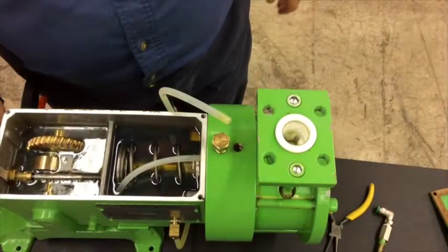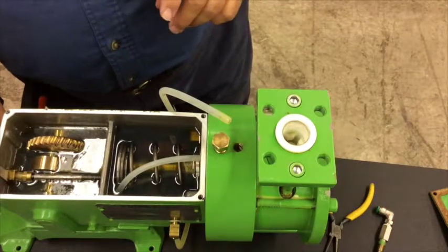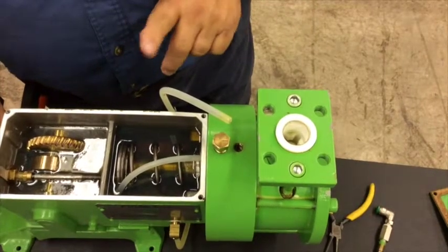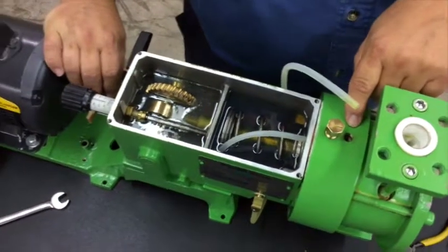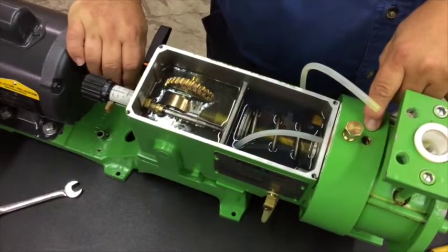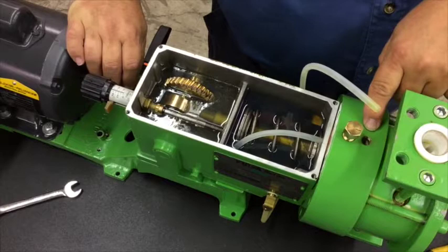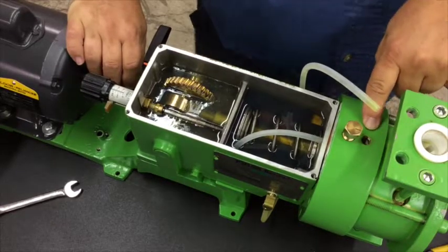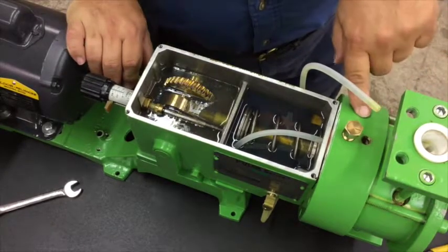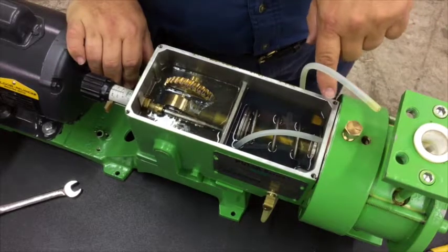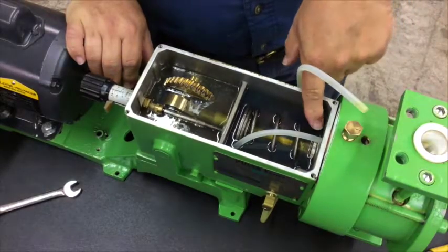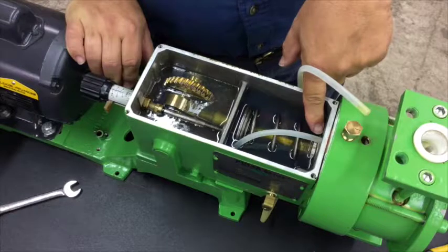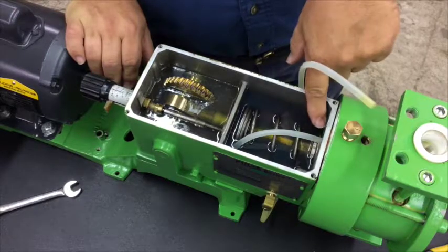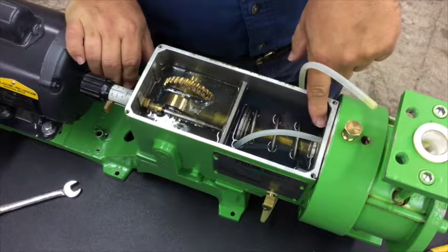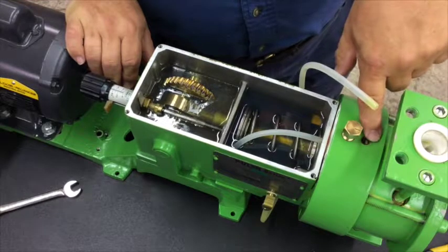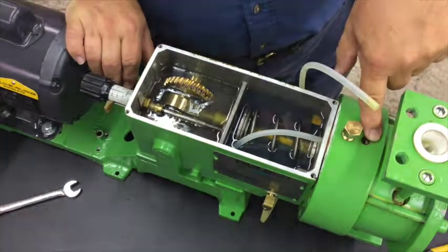Now what I'm going to do is move the piston forward by rotating the motor coupling, and I want to fill this air bleed valve port to the top with oil. Because what has happened is that the oil is in the pump head, but it's only at this level here, the same level as inside the front chamber. What I want to do is bring that oil level up into this port here to get all the air out of the system.